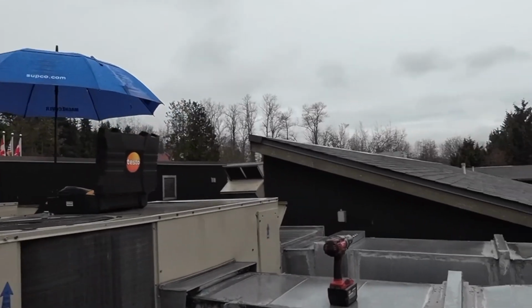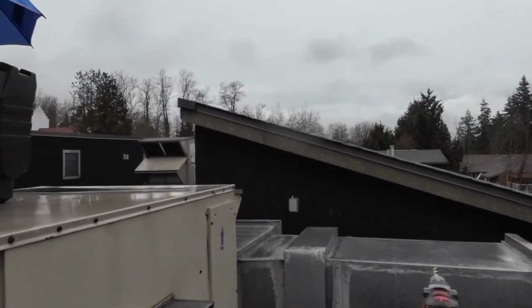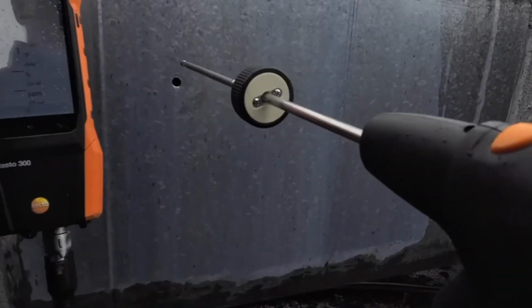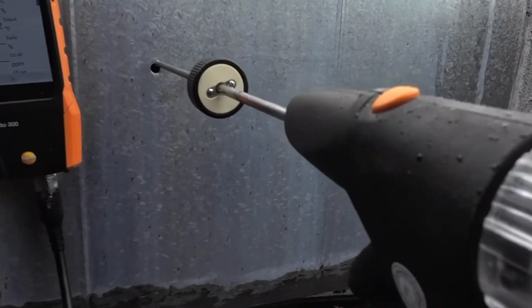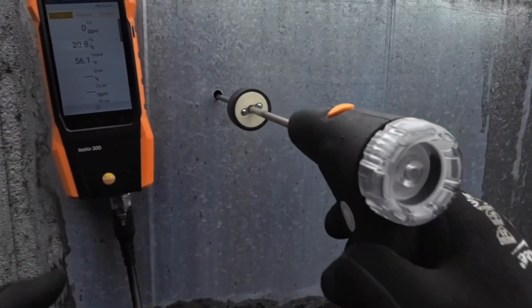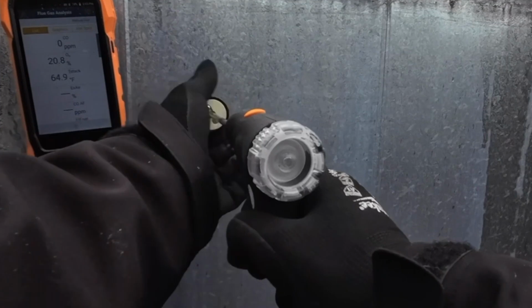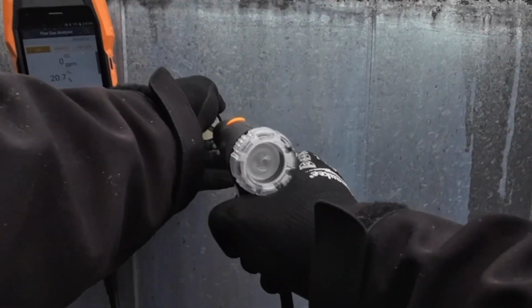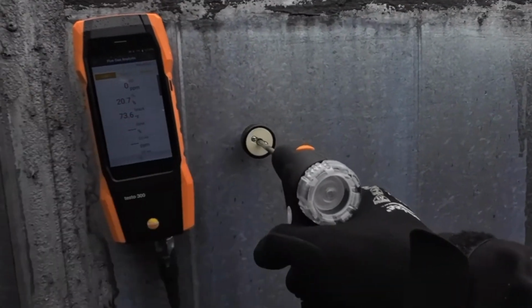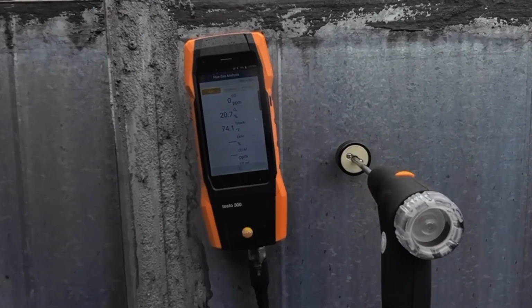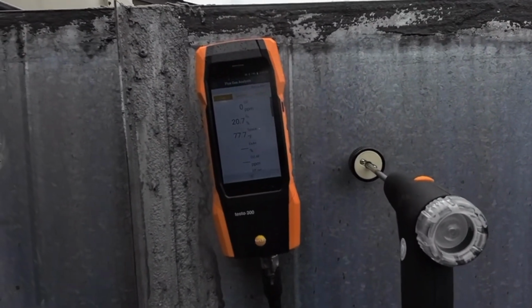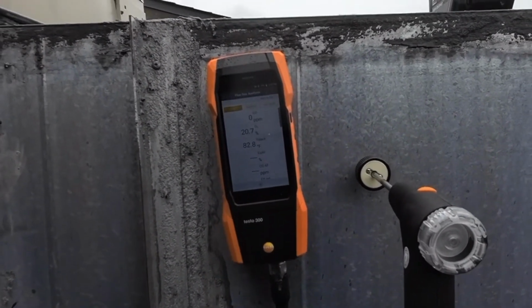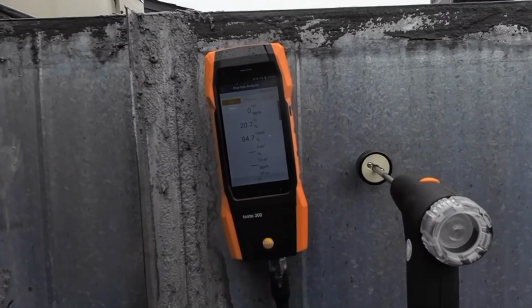Alright, so I drilled a hole into this unit here. We were getting over 3,000 parts per million. My unit actually shut off at 3,000. I have the safety on that. So now let's test and see what we got going on. I'll let it sit in there for a minute and see what's happening here today. CO parts, stack temperatures rising. The heat is on.